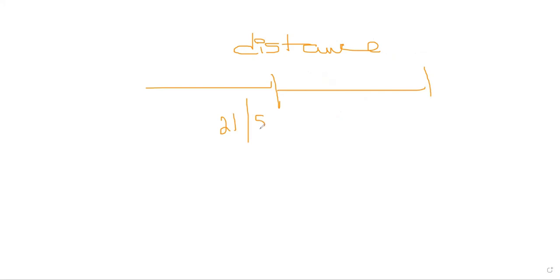Again, I will show you the differential protection, low impedance, high impedance settings, and restricted earth fault settings in our next classes. So let's come to the very important protection, which is the distance protection and the line protection. What protections will generally be there in the line? We have distance protection, carrier send which is 85, 68 power swing, 79, 67 or 67N, 51N, and disturbance recorders, and over voltage, under voltage, and load encroachment conditions we have to consider, out of step. So many protections will be there, also in the differential protection.